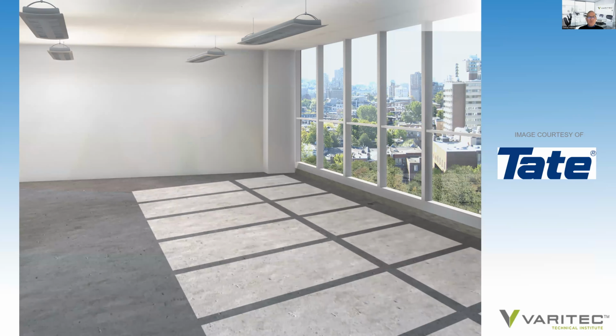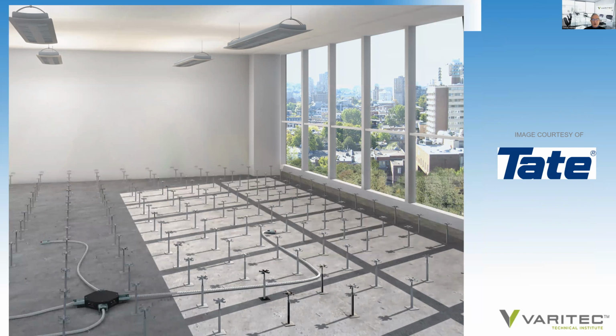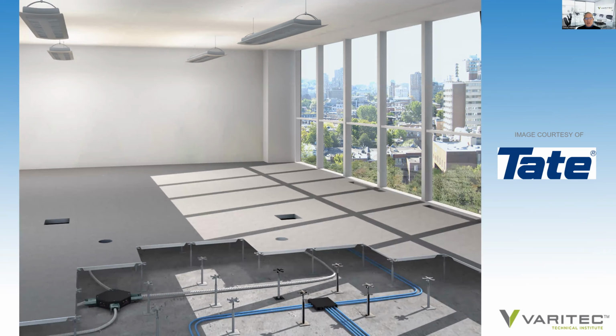Well, you start with a bare floor. And please be aware, these floors do not need to be polished, which is a construction savings to them. Because of the pedestal application, they can be easily mounted on coarse concrete floors while maintaining a level plane of floor above them. So the pedestals are mounted first, and any cabling that is associated with them would be installed. The floor is then installed.